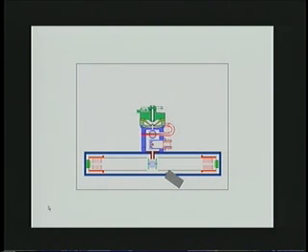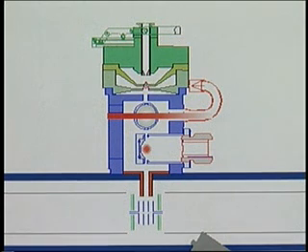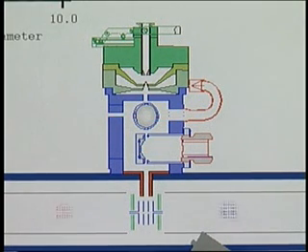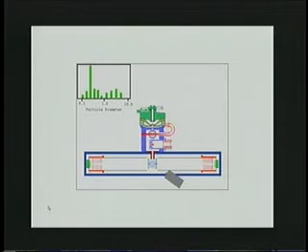Basically, the lasers are on. They're actually oriented perpendicular to one another, so we only look at the particles that are going right through the center of the system. Here comes a particle, scatters light, fire, chemical analysis. There's the chemical composition of one particle, and this is the size of those particles growing in the size distribution. So it just does one particle after another on a continuous basis.